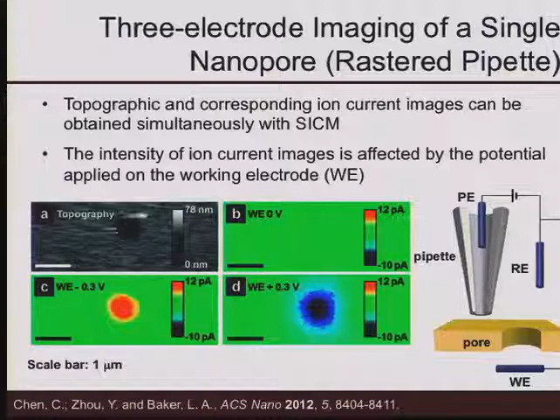If we hold this working electrode, so these are held at constant potentials, if we hold the working electrode at ground, we don't see any change in the ion current or the conductance at that pore. Right? If, however, we change the potential of this working electrode, then we notice a change in the current that's observed at the pipette in this case. And so if, for instance, we hold this potential at minus 300 millivolts, we notice there's an increase in the current that we measure. And if we hold the pipette electrode, or the working electrode, at 300 millivolts, there's a decrease in the current measured at the pipette.